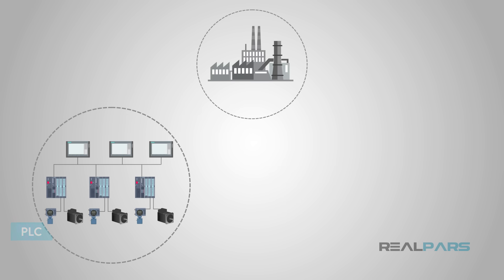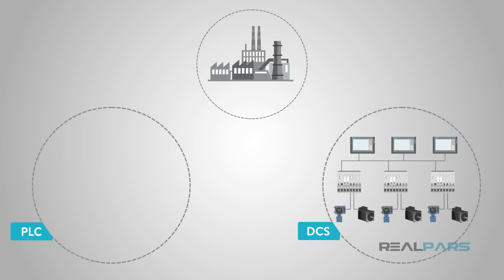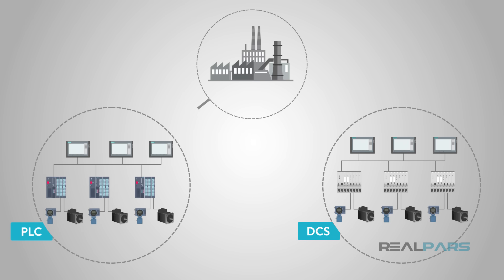As you can tell, there are likely advantages and disadvantages in both systems. The takeaway is that with today's technologies, either system can control an entire plant. Which system is chosen will likely take the advantages and disadvantages into account, as well as system costs. In summation, the DCS has autonomous controllers dispersed throughout the entire plant — if a controller fails, the entire plant doesn't necessarily get impacted — and it has onboard monitoring and control that saves development time. A single PLC is a single point of failure, but a connected PLC system can have nearly the same security and robustness as a DCS.